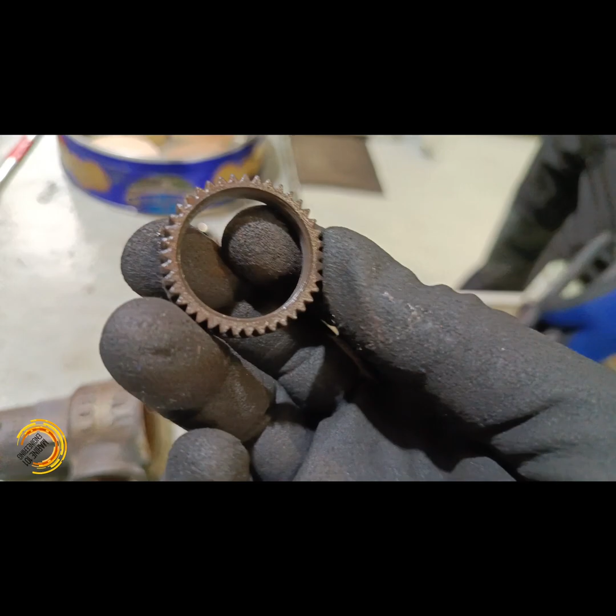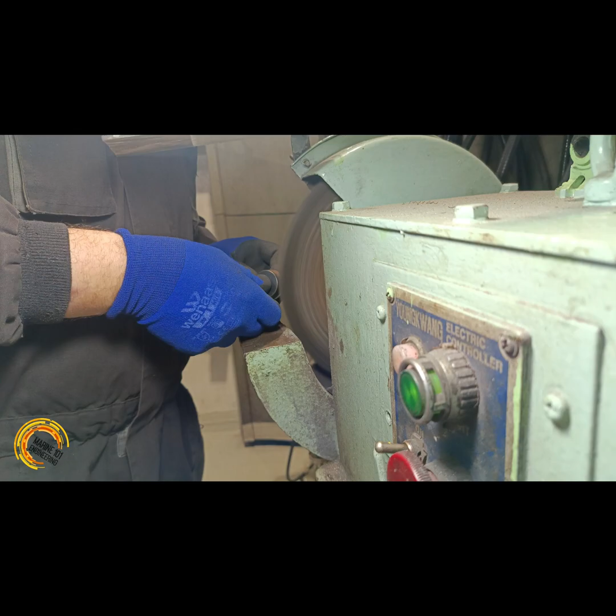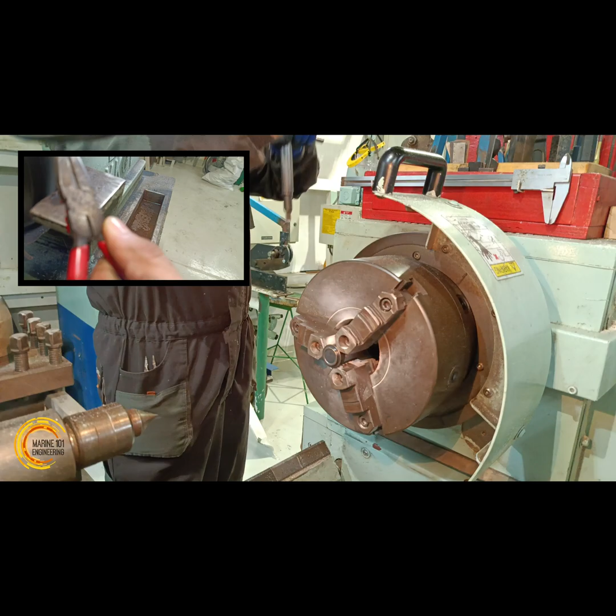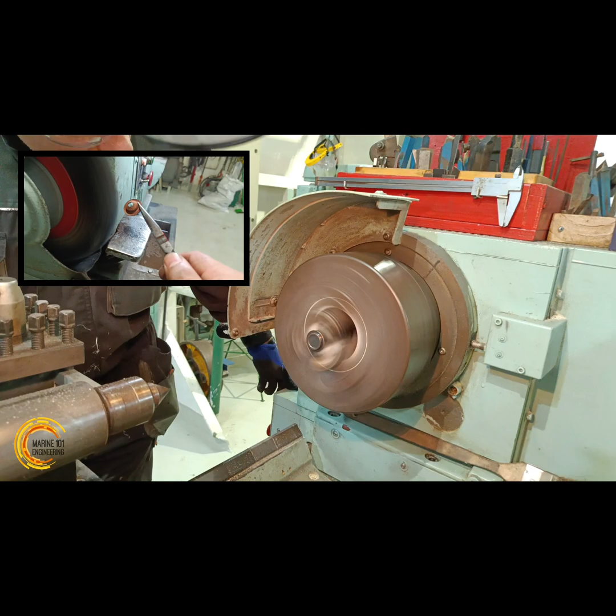The problem was this valve has been leaking even without reaching the set point. Hence a repair job is needed. Upon inspection of the parts, worn valve seats were observed due to pittings. The best remedial option entails a refacing operation on the lathe machine.